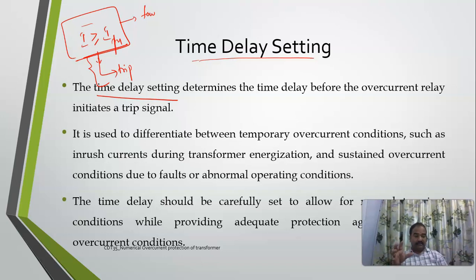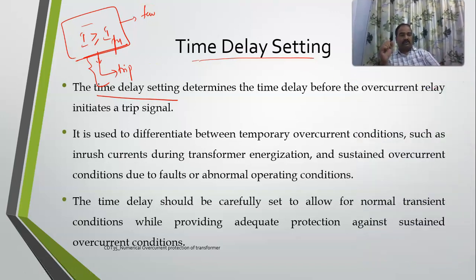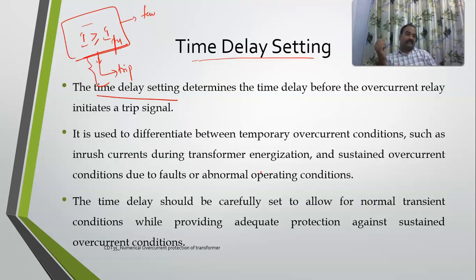During transformer energization there might be huge inrush currents lasting only a few microseconds, or transients due to lightning, which may not need to be treated as overcurrent conditions. So the relay waits and watches. The time delay setting must allow for normal transient conditions while ensuring adequate protection is provided for sustained overcurrent conditions. If the fault is sustained, proper action should be taken; if it lasts only a few milliseconds or microseconds, the relay need not operate. Time delay setting must be carefully chosen.